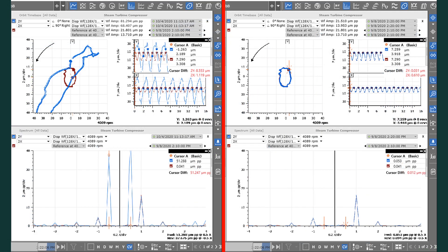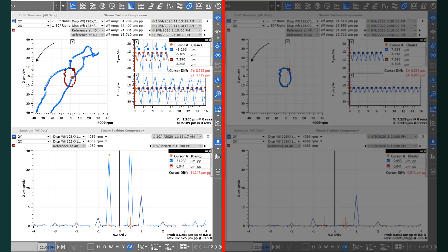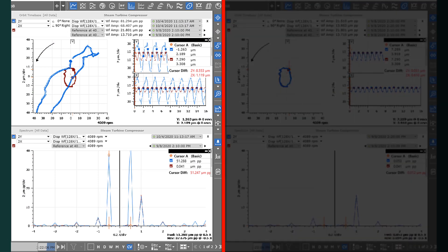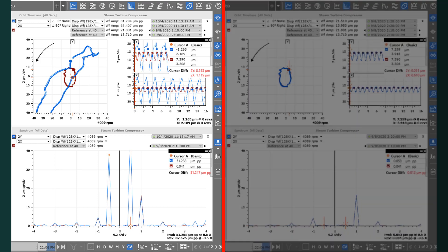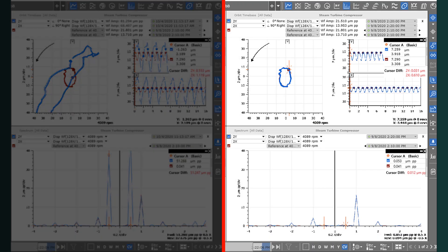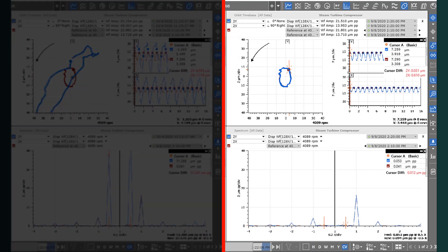The initial response of the rotor during the rub condition is shown on the left. After operations acted upon engineering's guidance, thermal stabilization of the compressor was achieved, and the rub condition was removed returning the rotor response to normal behavior which is shown on the right.